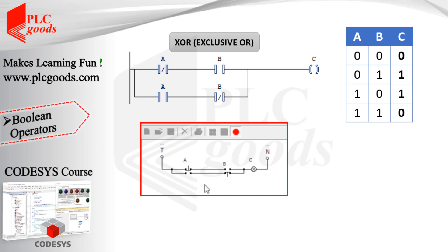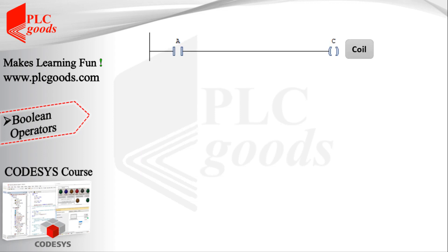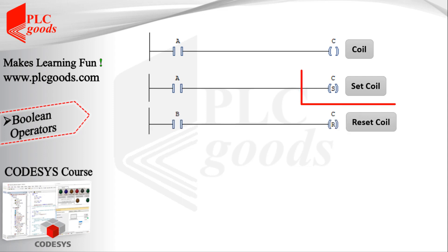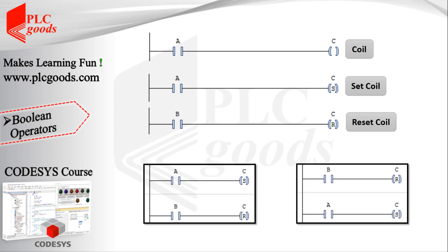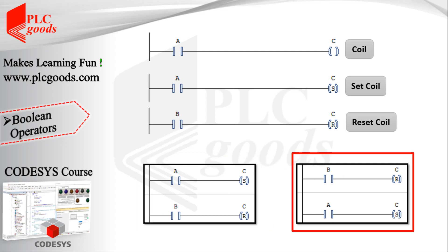Another important advantage of using PLCs is that they support a variety of instructions. For example, in addition to simple coils, set and reset coils can be used to turn on and off an output. The set coil is only used to set the state of a specified output to one, for example to turn on the C output. The reset coil is only used to reset a specified address to zero. Note that PLCs update all outputs at the end of each program execution, so if both instructions are activated for the same output, the last one wins. In the next videos, other instructions such as timers and counters will be explained.